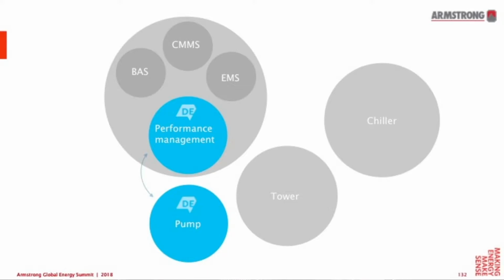But what a DE pump also does, which we mentioned earlier, is it doesn't just look at itself, it looks at the entire system. So once you have the DE pump in the system, it actually brings you savings on the condenser side as well as the chiller side. So the total savings with that move is approximately 10%, and this is totally cash flow positive from day one.